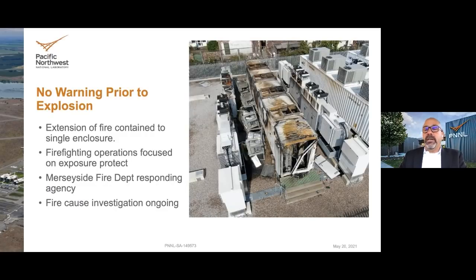This system was not required to include any fire suppression or deflagration venting. Deflagration venting is essentially blowout panels that direct any pressure wave in a certain direction. These holes in the top of this enclosure were actually where the HVAC units, laying down here on the side, were tossed off.